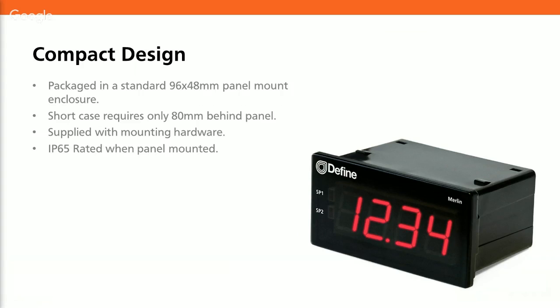The Merlin fits into a standard 96 by 48 millimeter panel mount cutout. What sets it apart from many other products is its short case depth. It only requires 80 millimeters of space behind the panel to have enough room for the instrument and all of the connectors. We do also supply mounting brackets with the Merlin, and all the mounting hardware fits behind the panel, so it's a nice clean install. When you properly install the Merlin, it's rated for IP65, making it suitable for harsh environments.